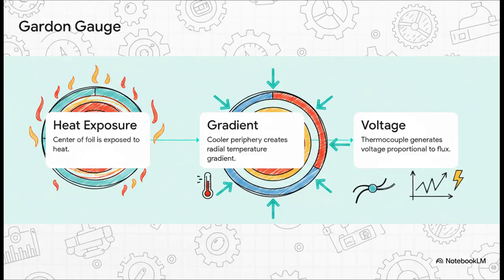A really classic example of this is the Gardon gauge, and its working principle is fascinating. Let's break it down step by step. First, the center of a circular metal foil is exposed directly to a heat source. Second, the outer edge, the periphery, is intentionally kept cooler. This creates a distinct radial temperature gradient from the hot center out to that cool edge. Finally, a thermocouple junction placed strategically between the center and the edge generates a measurable voltage based exactly on that temperature difference. It's an elegant physical reaction translated into readable data. We're literally turning heat into math.